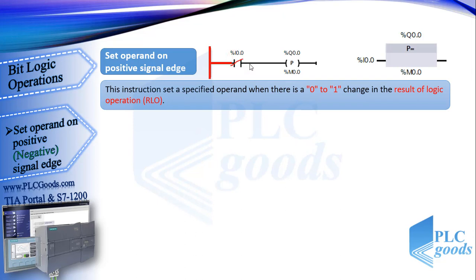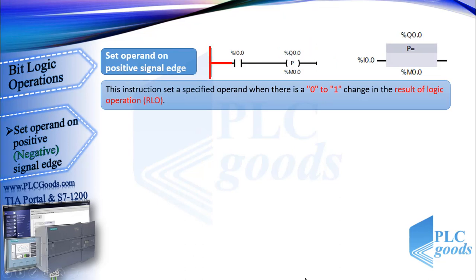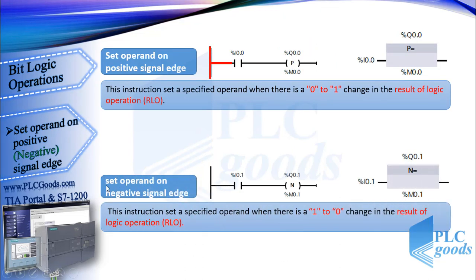When I 0.0 changes to close, the RLO changes from 0 to 1, which this instruction detects. So this instruction will change the state of Q 0.0 from 0 to 1 for only one program cycle, which is about 5 ms. Similarly, set operand on negative signal edge works when there is a 1 to 0 change in the RLO.